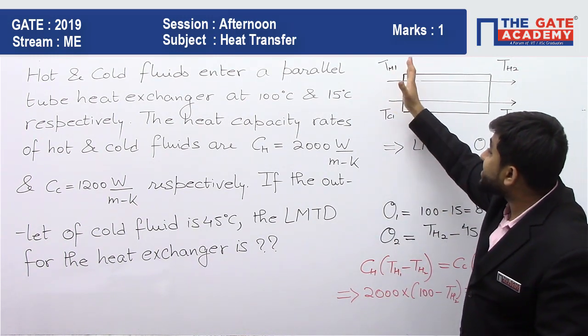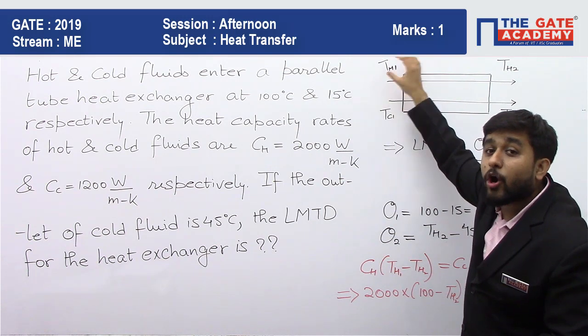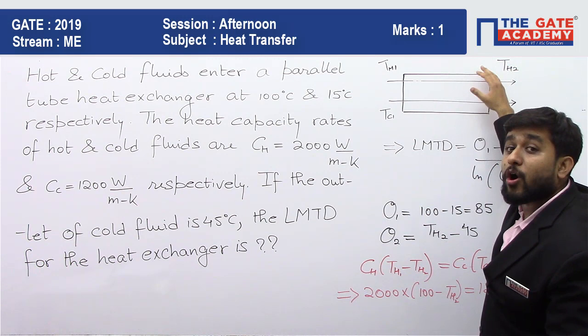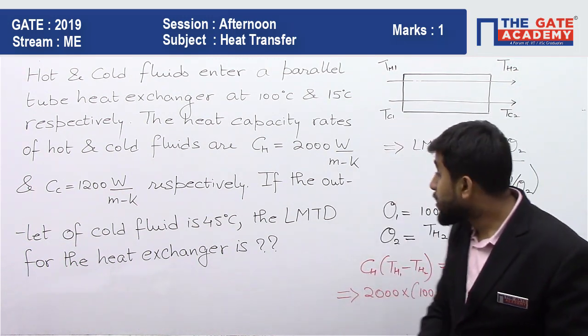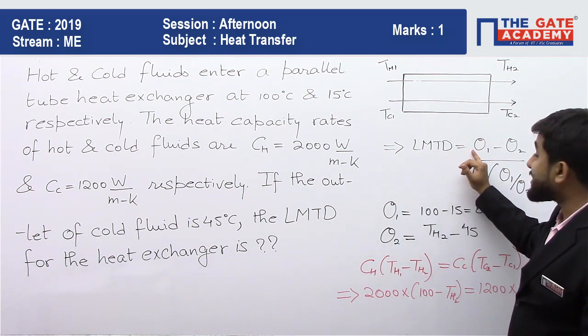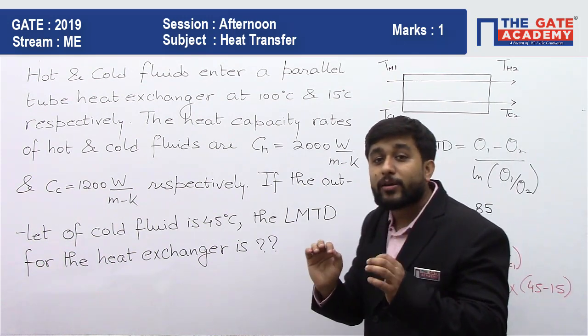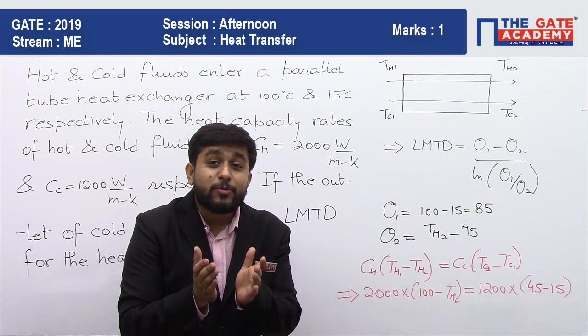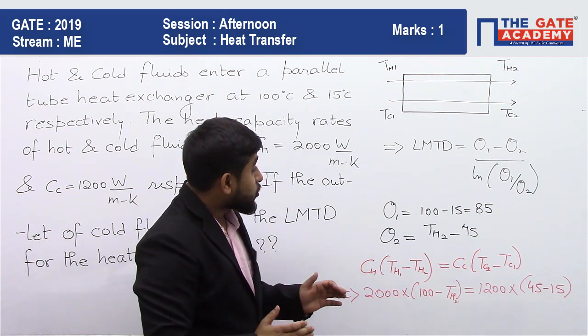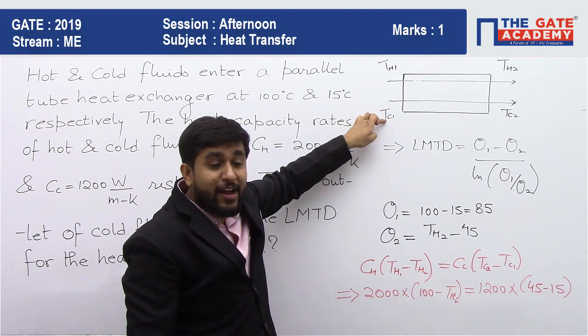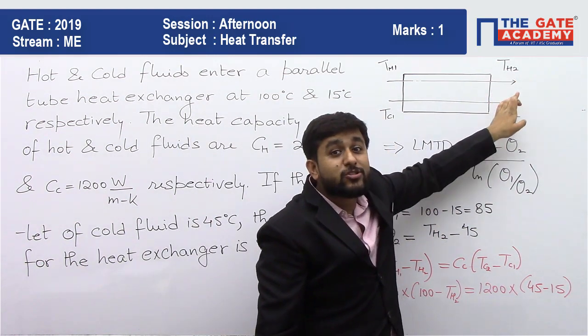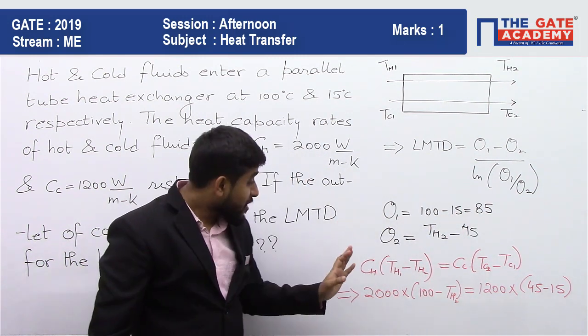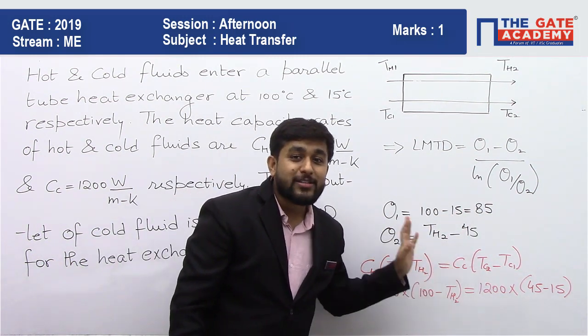Considering the side where the hot fluid enters as side 1 and where it exits as side 2, we write LMTD as (θ1 − θ2) / ln(θ1 / θ2). Here θ1 is the temperature difference between hot and cold fluid at side 1, so θ1 = TH1 − TC1, and θ2 = TH2 − TC2. For us, θ1 = 100 − 15 = 85°C, and θ2 = TH2 − 45, which is still unknown.